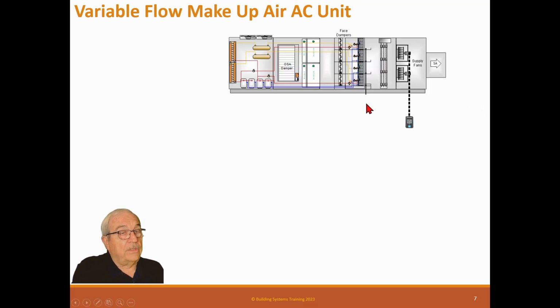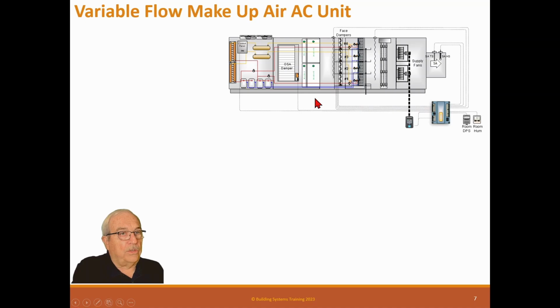So basically this is a unit that has 4 different segmented cooling coils, 4 compressor circuits, and variable speed fans to do the system. So what happens is we have these isolation face and bypass dampers basically. So we can open one damper and limit it to just one coil that's sized correctly for that one coil load. So when we have a load out there, in this building, we have DDC, and we can control each of those separately. And we'll go through the sequence to show how that works. So basically, we can tune this refrigerant circuit for just 25% flow, like a full package unit at full flow at that one system. And then we can keep increasing the capacity as we go up or down. We can do that. So we have variable speed drive on the forward curve.